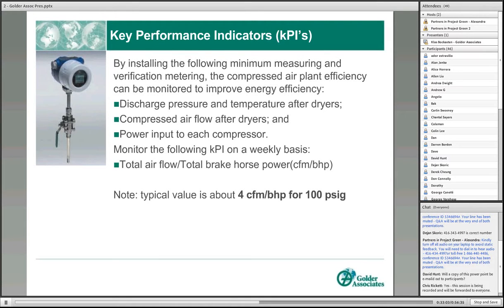To be able to assess the efficiency of a system in the compressor plant, in adding some of the key points you can identify out in the plant, it will be to have a few measuring tools on the system. And the key ones are really to have a master pressure gauge or a discharge pressure gauge, plus a temperature gauge on the compressed air as it leaves the compressor room. In addition to that, a compressed airflow measurement device, and also the power input to each of the compressors. By measuring the total CFM that you're producing at any one instant, and simultaneously adding up the kilowatts consumed by the compressors, you can easily do a calculation by CFM over brake horsepower or CFM by kilowatts.